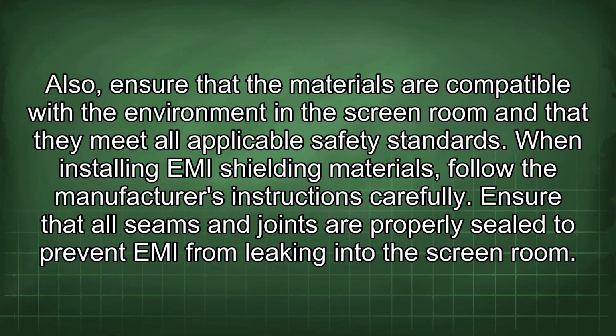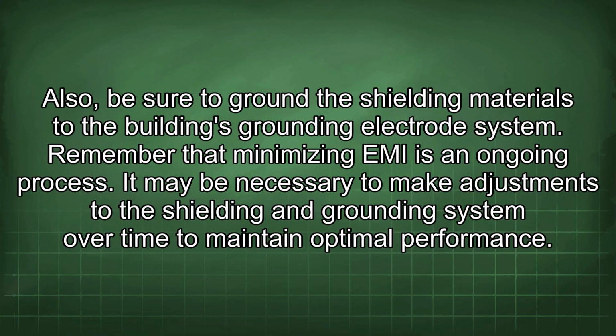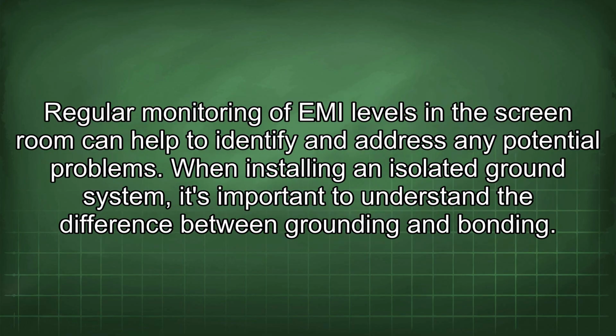When installing EMI shielding materials, follow the manufacturer's instructions carefully. Ensure that all seams and joints are properly sealed to prevent EMI from leaking into the screen room. Also, be sure to ground the shielding materials to the building's grounding electrode system. Remember that minimizing EMI is an ongoing process. It may be necessary to make adjustments to the shielding and grounding system over time to maintain optimal performance. Regular monitoring of EMI levels in the screen room can help to identify and address any potential problems.